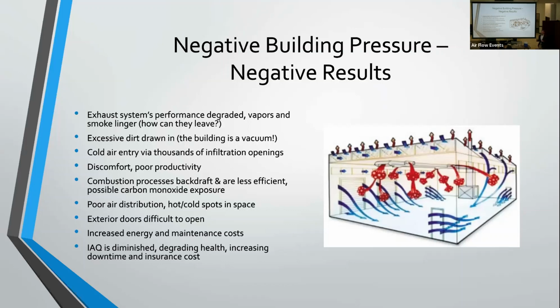You've got poor air distribution in the space. Exterior doors also become difficult to open, which maybe doesn't seem like a big deal, but I've heard stories where the space was under such negative pressure that an employee was going through an exterior door and it slammed shut so hard on their arm that it broke their arm. So obviously that's not good for well-being, but there's also downtime and insurance costs associated with that injury. Like I said, you've got poor air distribution and stratification in that space.